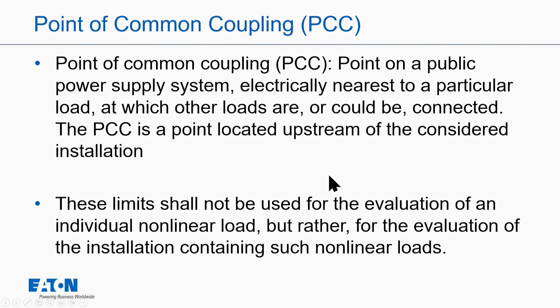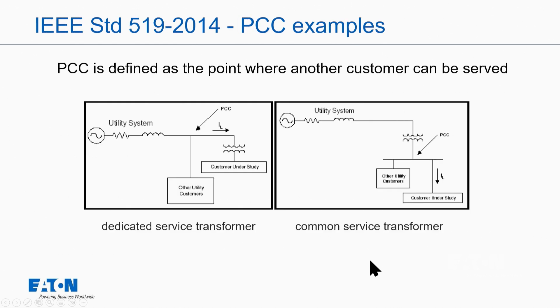Let's take a look at a couple slides. The PCC on a public power system is really the point where that load — or you as a load — from the utility perspective, are or could be connected. When we have multiple people at the secondary or primary of a transformer, the transformer is not necessarily relevant; it's where you could be connected. Importantly, per IEEE 519, these limits should not be used for the evaluation of an individual nonlinear load, but rather the evaluation of the installation containing such nonlinear loads — meaning the overall system effect, not just one load.